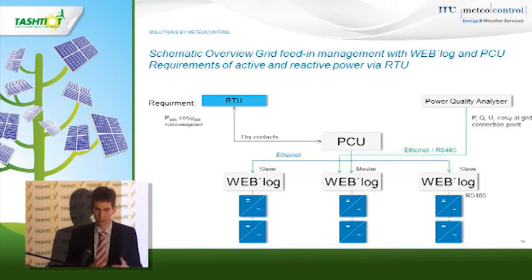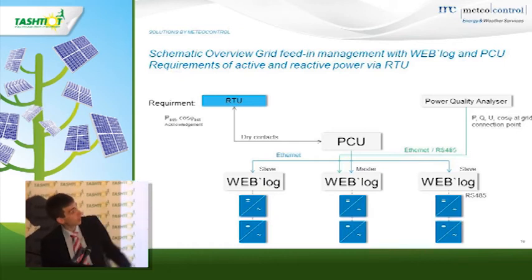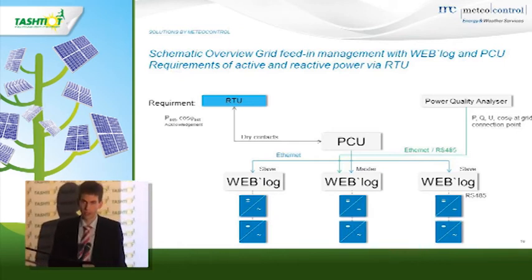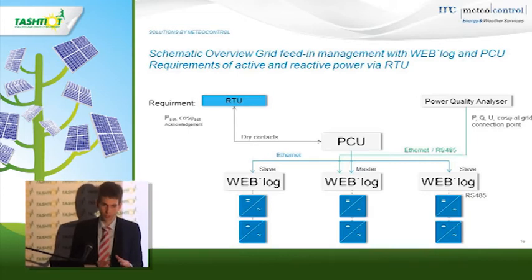Okay, so what does such a solution look like? We have the requirement by the utility, the RTU in this case, and we have an interface to the PCU, which is the power control unit, a device from meteocontrol, which is the interface between utility and the plant control. On the right side on the top, we have the power quality analyzer, which is measuring on the grid connection point to do this feedback control.